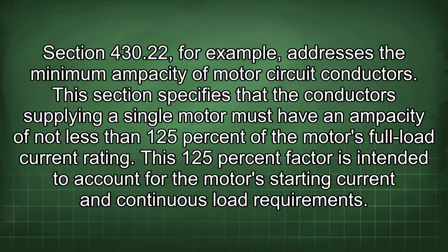Section 430.22, for example, addresses the minimum ampacity of motor circuit conductors. This section specifies that the conductors supplying a single motor must have an ampacity of not less than 125% of the motor's full load current rating. This 125% factor is intended to account for the motor's starting current and continuous load requirements.